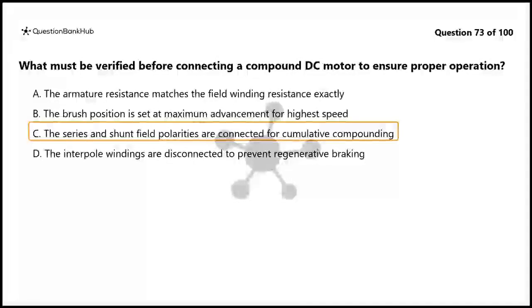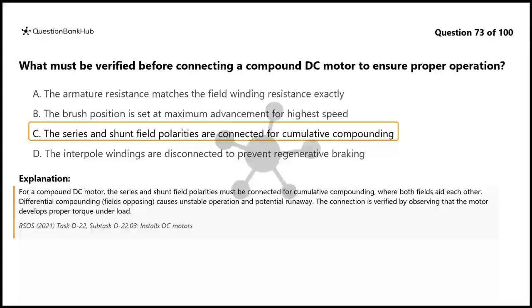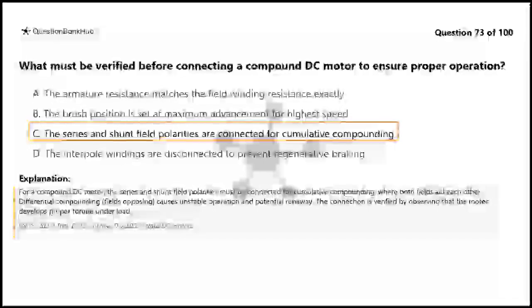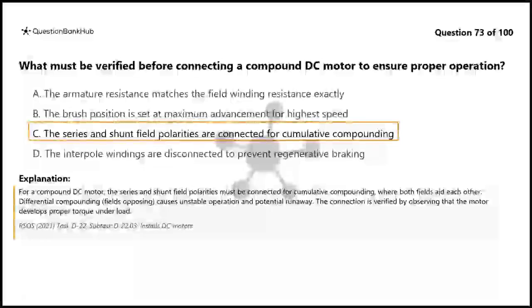The correct answer is C. The series and shunt field polarities are connected for cumulative compounding. For a compound DC motor, the series and shunt field polarities must be connected for cumulative compounding, where both fields aid each other. Differential compounding, fields opposing, causes unstable operation and potential runaway. The connection is verified by observing that the motor develops proper torque under load.